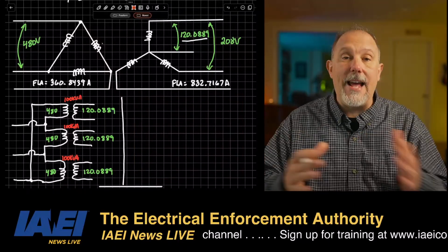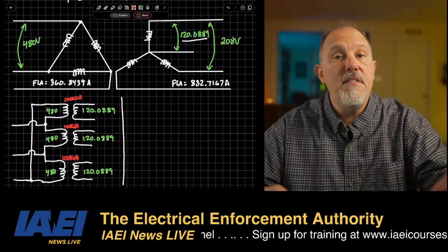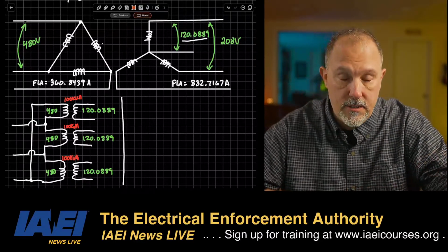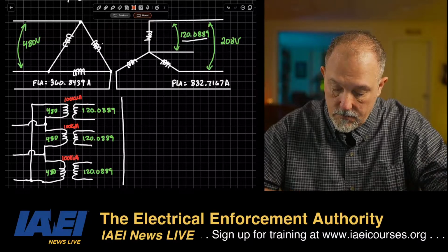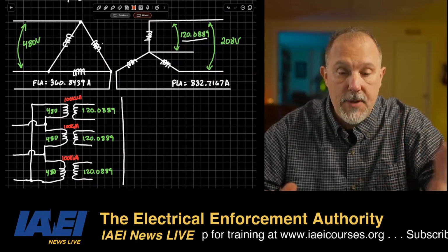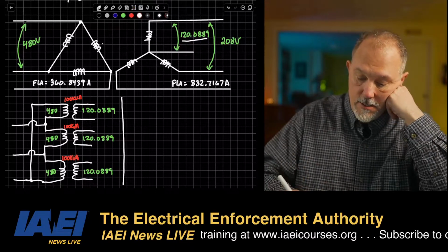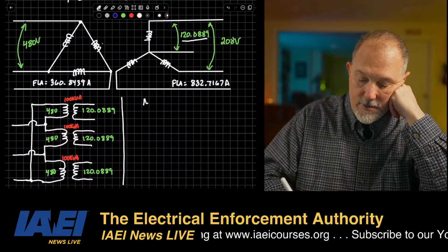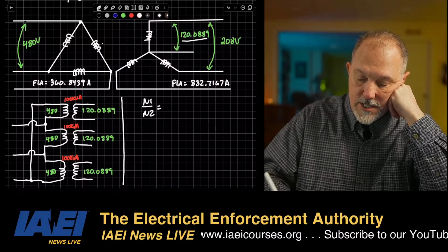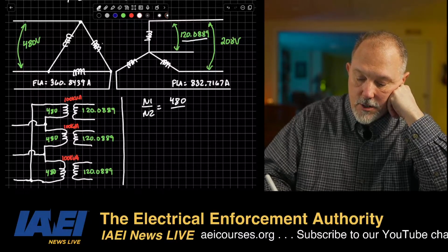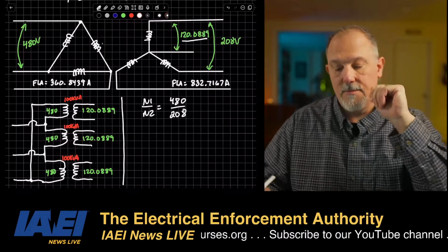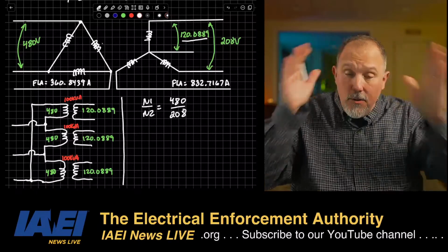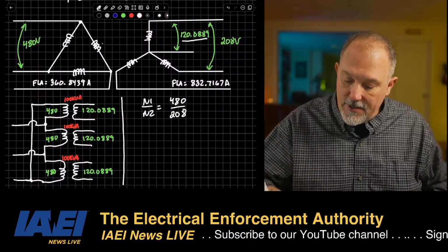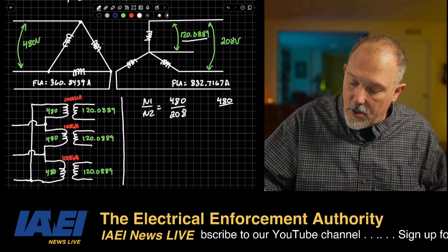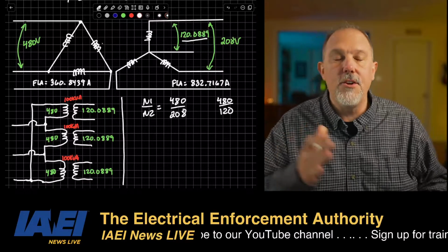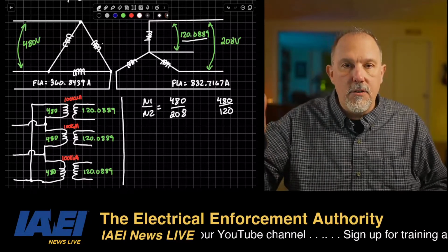Now, if I want to reflect, I'm going to use my three-phase method of reflecting my currents. For the three-phase bank, my N1 over N2 is equal to 480 over 208. Now, I'll have people say, no, Tom, N1 over N2 is 480 over 120. And you're right for a single-phase transformer.